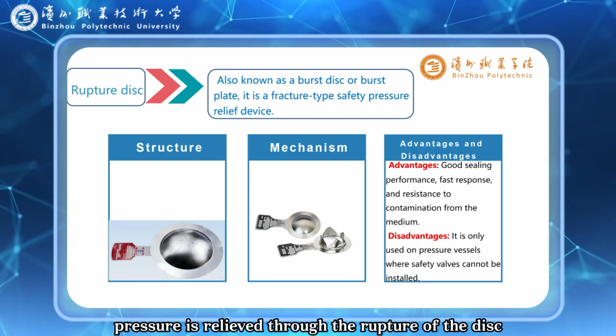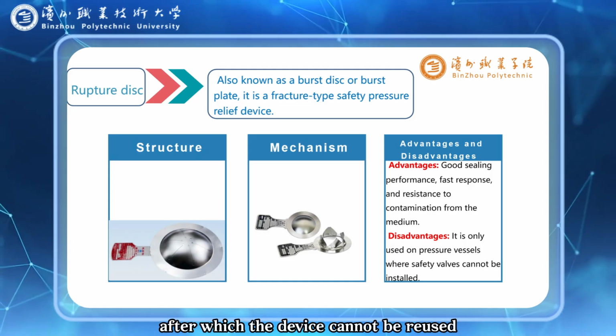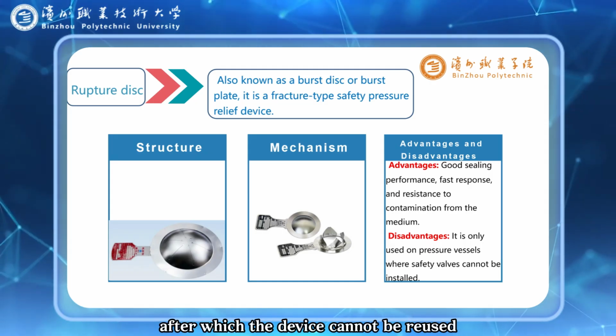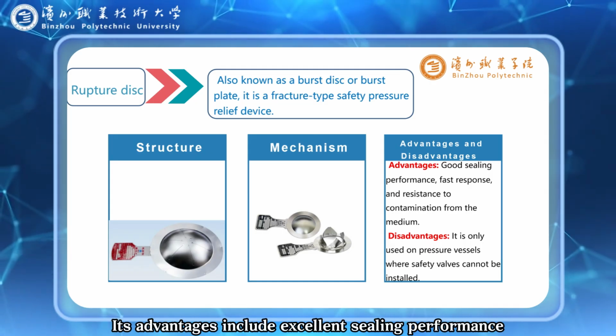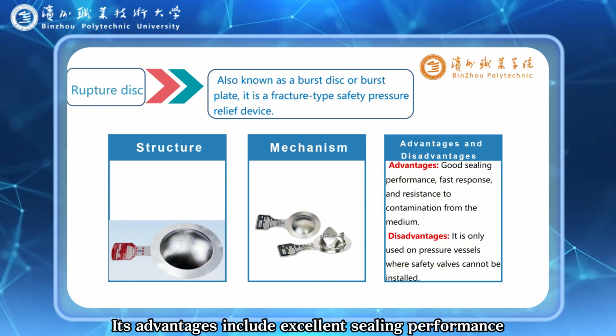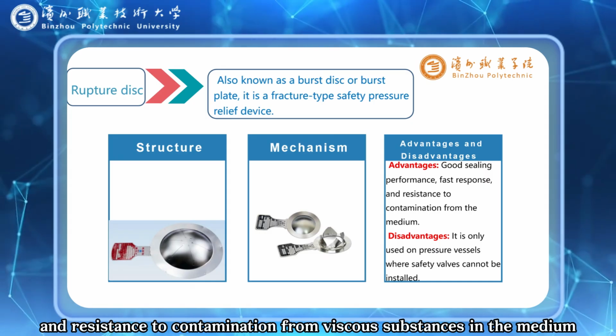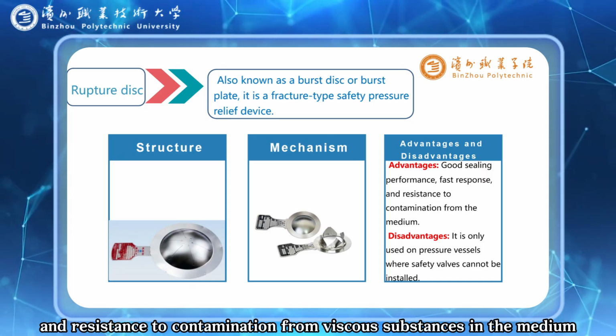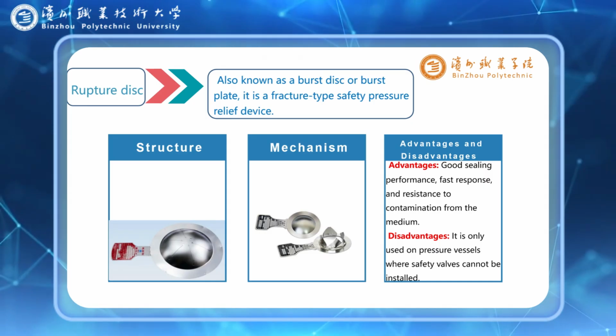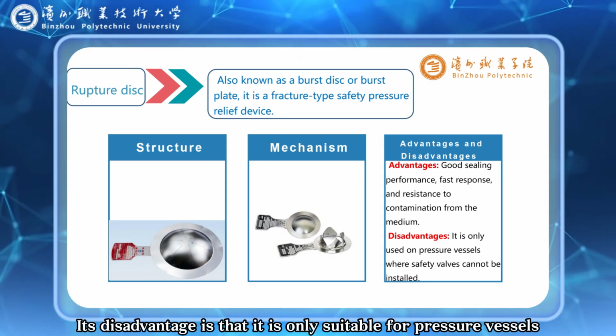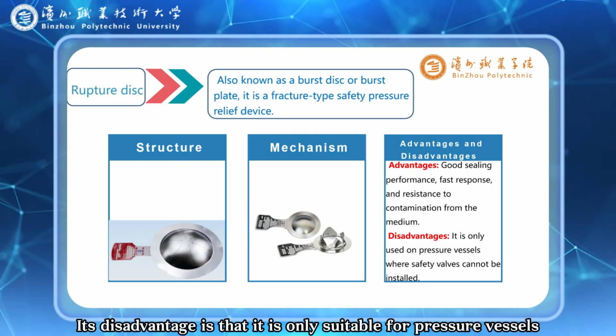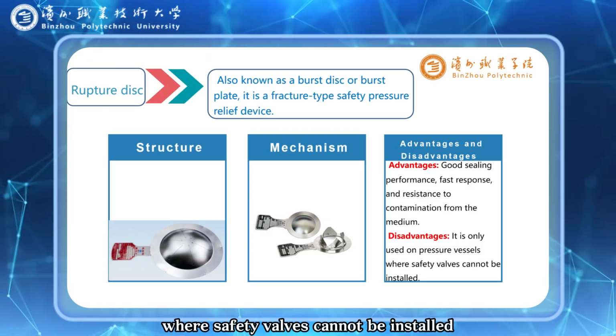Pressure is relieved through the rupture of the disc, after which the device cannot be reused. Its advantages include excellent sealing performance, rapid response, and resistance to contamination from viscous substances in the medium. Its disadvantage is that it is only suitable for pressure vessels where safety valves cannot be installed.